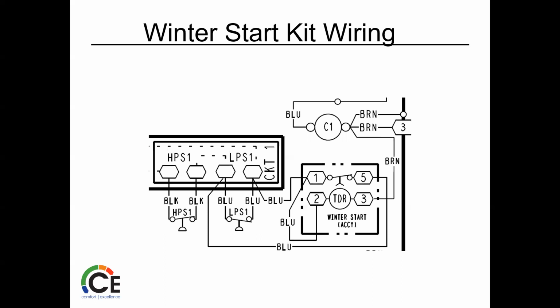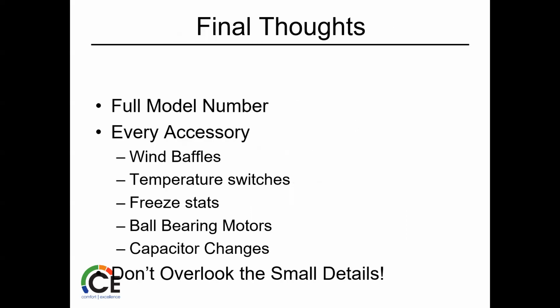So one wire comes in on the intake side, and one wire comes off on the outlet side. And then if the switch does operate, but we're in low ambient mode, then everything's going to keep going. I have heard a few guys say maybe there's a delay between the two and it shut off and kicked right back on. But for the most part, you never know what happened. So just make sure we're not cutting the low pressure switch. We're just adding this on those terminals. And then just 1 to 2. And then of course it sends out a common and a signal to the motor to tell it to keep rolling, to the system, forgive me.